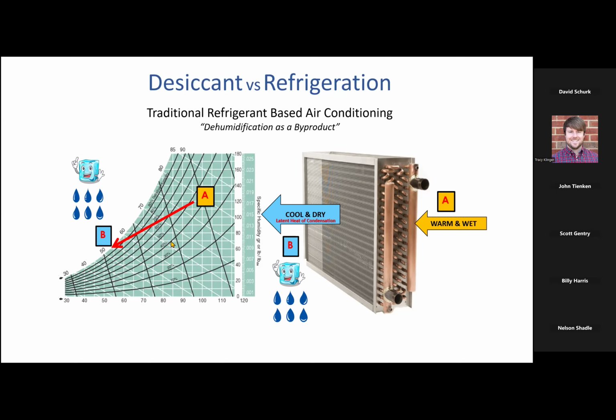The other problem is simply this. What if I need to be around 10 or 20% relative humidity or less? I have to continue to drop the temperature of that air, but I can only drop it so far. And here at 32 degrees Fahrenheit, the train comes off the tracks, right? If I create a cold coil surface temperature of 32 degrees Fahrenheit and the moisture in the air is condensing onto that surface, it begins to frost, it freezes, I create a block of ice, and I get no airflow.